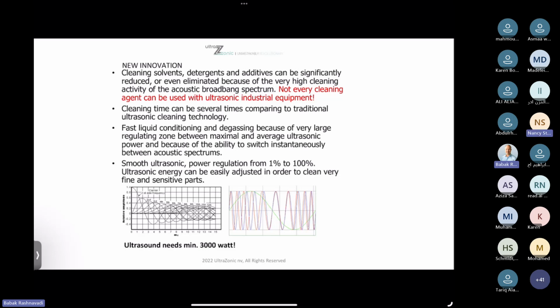Now, our ultrasonic cleaner actually has power regulation. We have 3,000 to 5,000 watt power, while when you go to Elma or another brand, they have 500 watt, 800 watt. You can of course imagine that when you have less power, it takes more time to clean an instrument. So we were also considering creating a device that can clean all your instruments fast and very efficiently. Most of the time it's on 80% of power, but you can also minimize the power regulation so you can really just clean one instrument. There are so many possibilities to use our device and to create a very decent cleaning efficacy.